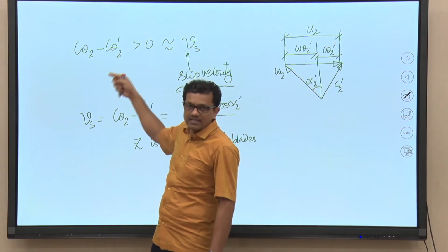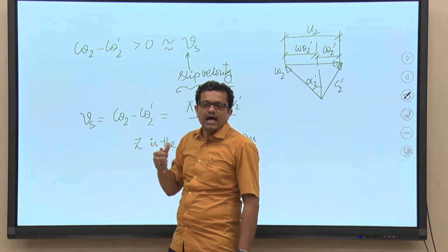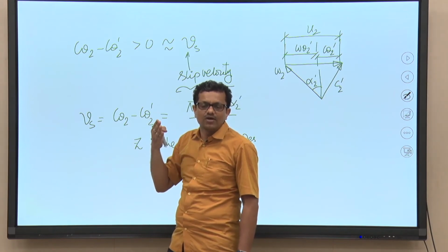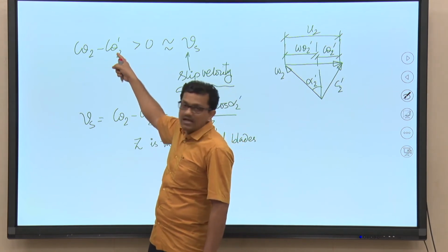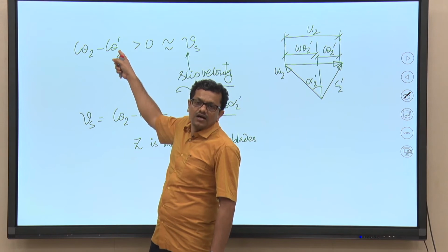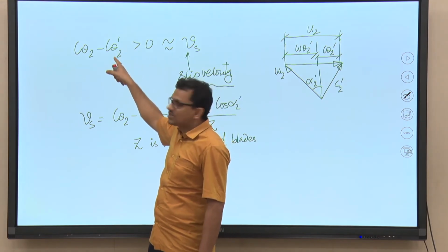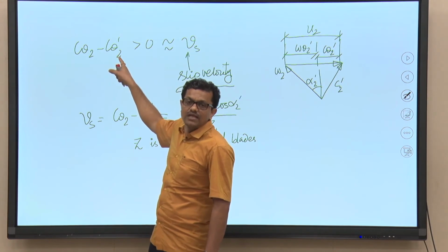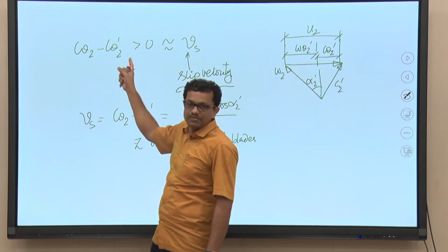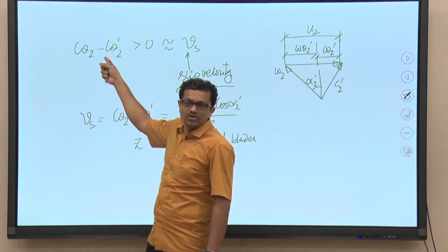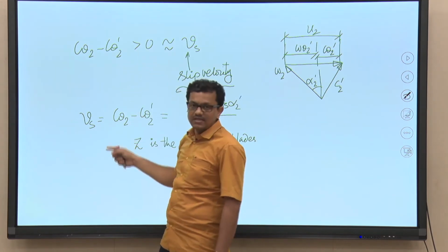But when the pump starts rotating, because of this rotationality effect a resultant force will be acting on the convex surface of the blade, which will eventually result in a diminished swirl component of velocity at the outlet, c theta 2 prime. So, this is the swirl component of velocity at the outlet when there is pump rotation, and this is as if when there is no pump rotation.